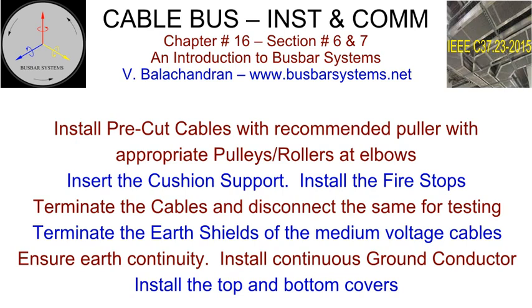Insert the remaining cable support blocks in position and align the cables. Ensure that an adequate length is left at the terminating end for clamping and negotiating up to the terminals. Insert the cushion support in the slot at the desired locations. Cushions are not required if the cable support blocks are made of maple wood. Install the fire stops at the designated location as recommended. Terminate the cables and disconnect the same for testing. Temporary insulating caps may be installed for the protection of terminations.